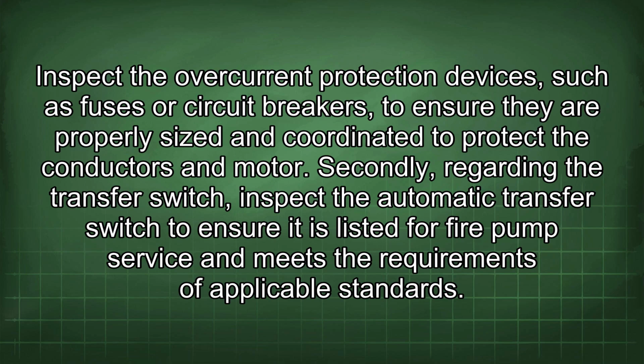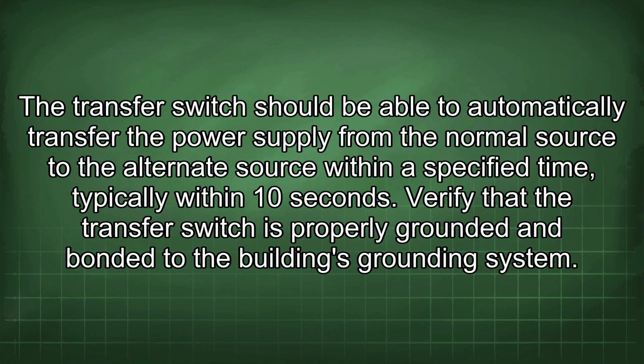Secondly, regarding the transfer switch, inspect the automatic transfer switch to ensure it is listed for fire pump service and meets the requirements of applicable standards. The transfer switch should be able to automatically transfer the power supply from the normal source to the alternate source within a specified time, typically within 10 seconds. Verify that the transfer switch is properly grounded and bonded to the building's grounding system.